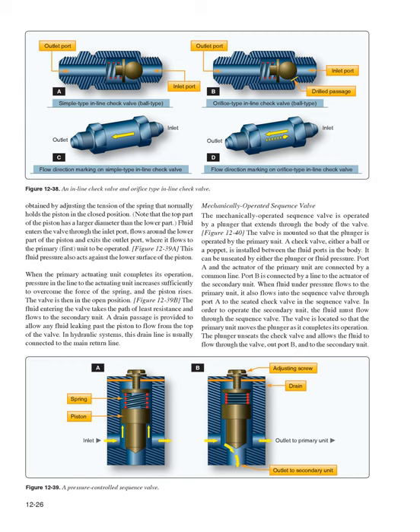When fluid under pressure flows to the primary unit, it also flows into the sequence valve through port A to the seated check valve in the sequence valve. In order to operate the secondary unit, the fluid must flow through the sequence valve. The valve is located so that the primary unit moves the plunger as it completes its operation. The plunger unseats the check valve and allows the fluid to flow through the valve, out port B, and to the secondary unit. Priority valves.